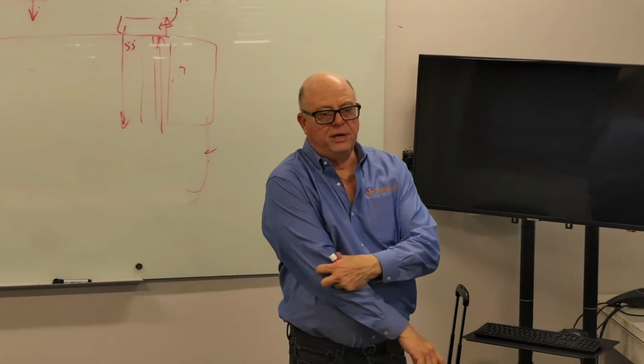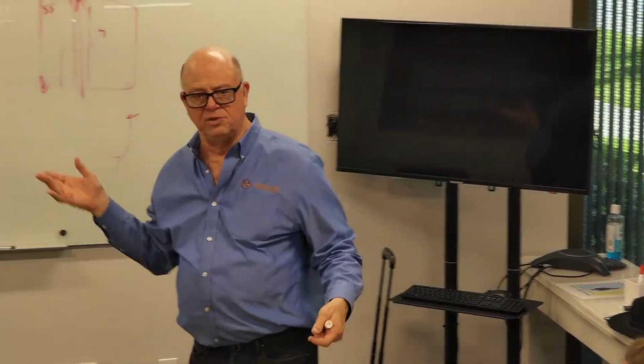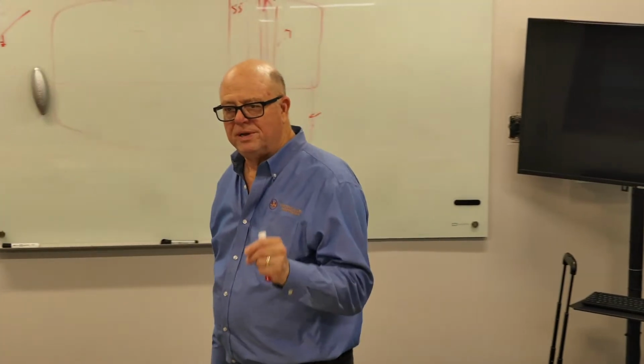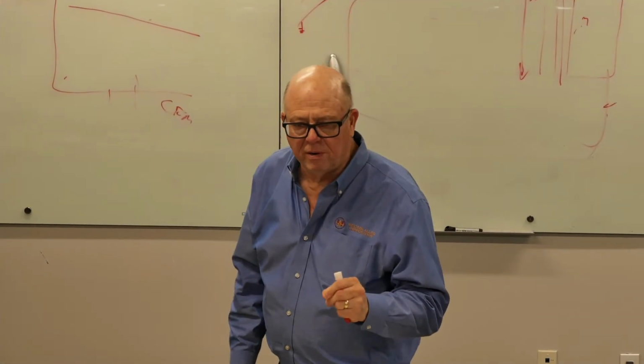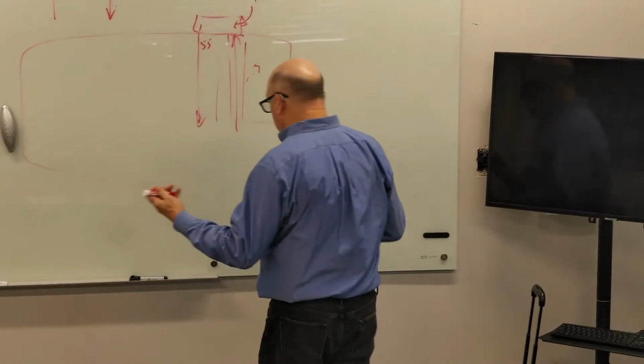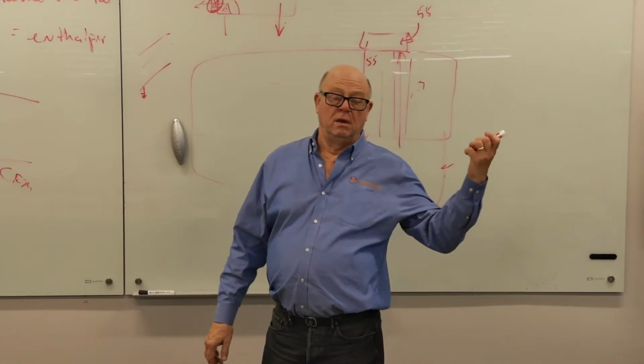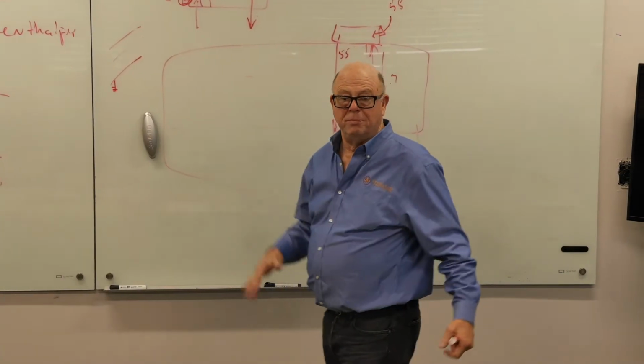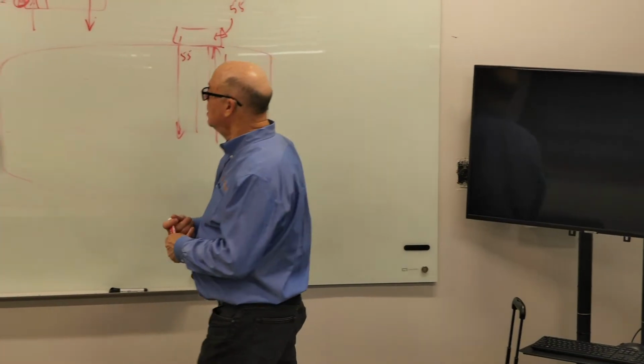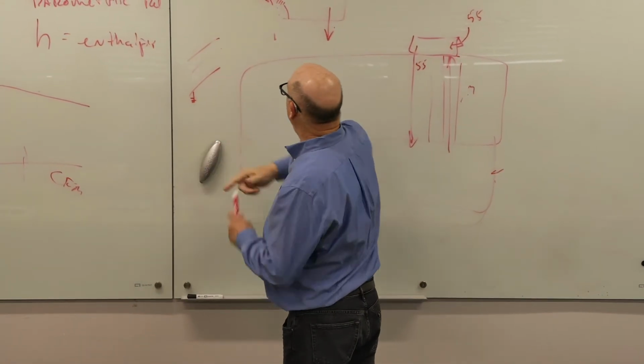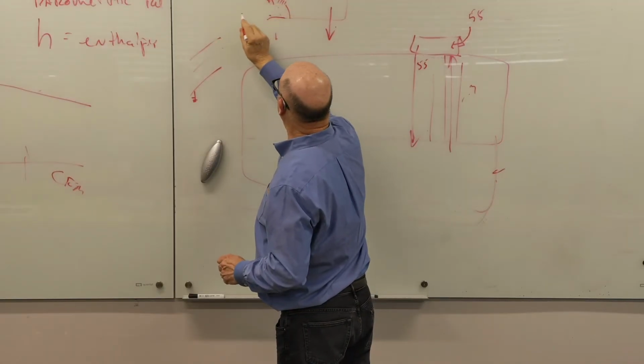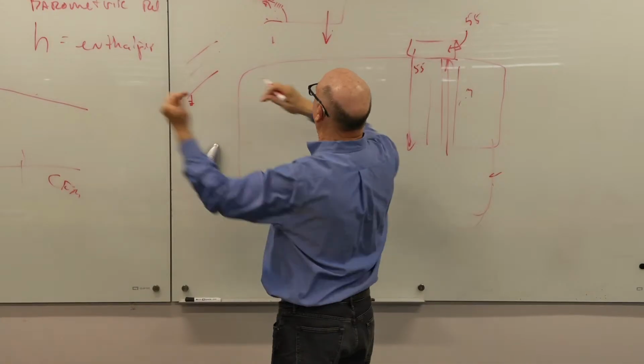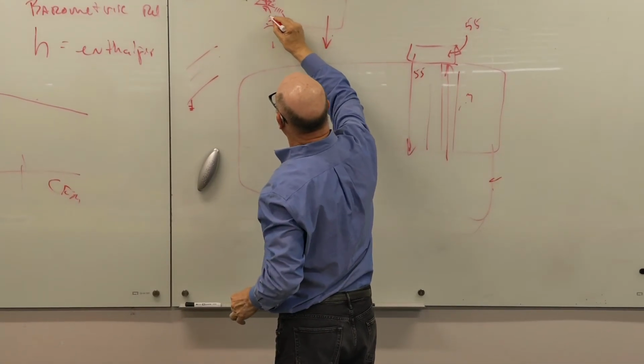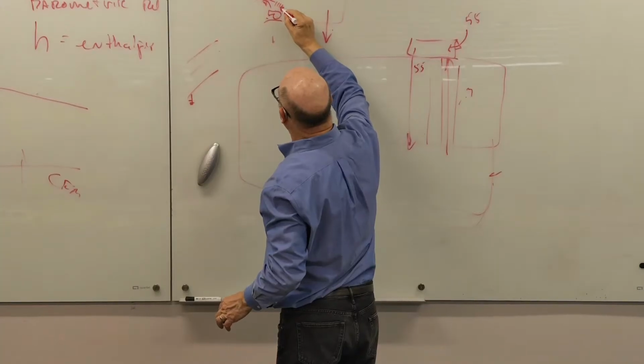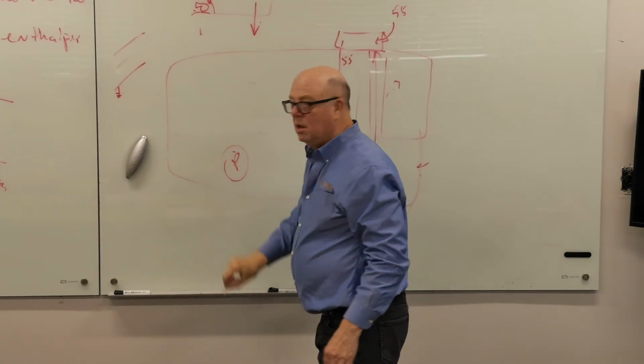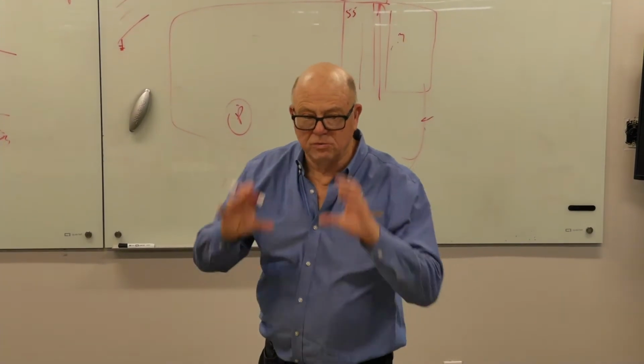But two things were happening by '91. One was people cared more about performance and sound. The other was that by '91, variable speed drives had been around for a while. So what Jim and I put together, and had our curb and economizer manufacturer build for us, was a slip-in housing that would slip in to the side. You take the panel off, you slip it in, and what you had was a centrifugal exhaust fan and a little variable speed drive, and you'd put a pressure sensor down on that bottom floor.